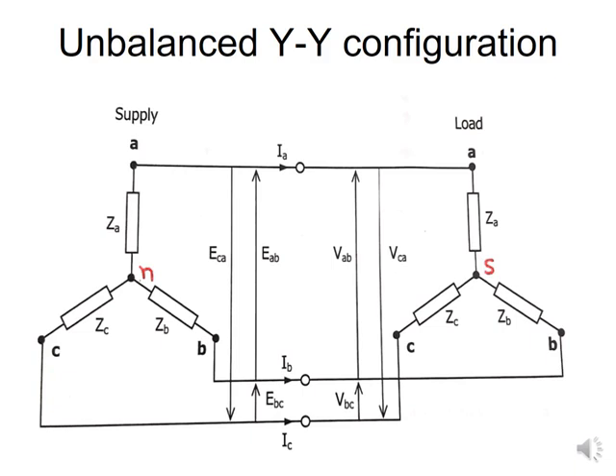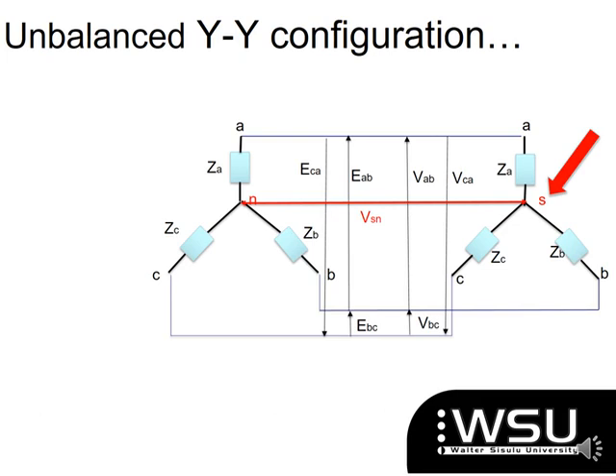I've made red markings: 'N' for the neutral on the supply side, and 'S' on the load side, which is another neutral. I'll explain why I've called it 'S'. On this slide I've drawn a line between my supply and load side showing this S value. For a three-phase system, we normally have the neutral point N. I'm introducing S on the load side, which is no longer at earth potential because we have an unbalanced system on the load side.